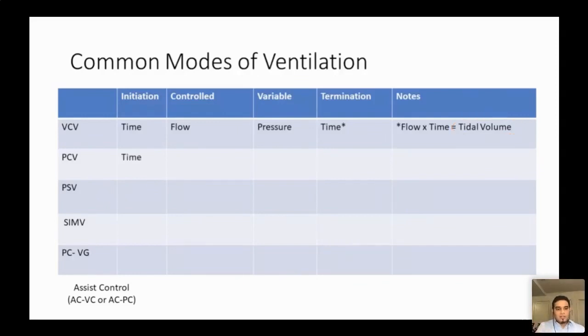Okay, what about pressure control? Well, for pressure control, again, we initiate the breath by time. By defining the respiratory rate, we control the pressure here, and the variable in this patient is the flow. It's the other way around from volume control.